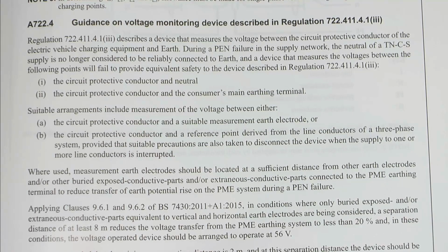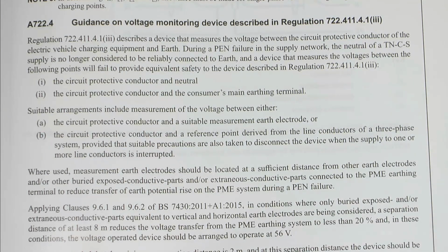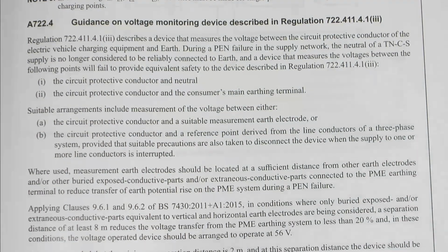Or B, the circuit protective conductor and a reference point derived from the line conductors of a three-phase system, provided that suitable precautions are also taken to disconnect the device when the supply to one or more line conductors is interrupted. And of course that only applies on a three-phase installation where you can actually access that reference point. Basically what it's talking about there is the neutral point or the star point on the three-phase installation.